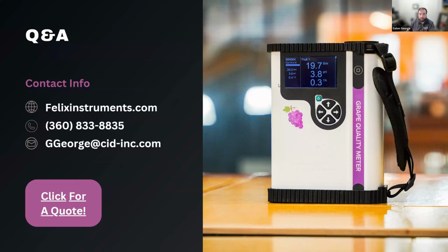This is a great question. I already kind of addressed that, but is there any specific requirement on the light condition? Your experience with similar NIR technology based equipment is that the measurement is largely affected by the ambient light environment. That is why we developed this proprietary device that has an internal reference shutter. This internal reference shutter is used at the start of every single measurement that we take. And what it's going to do is it's actually going to baseline every single measurement based on the ambient lighting conditions. And so it zeroes out those ambient lighting conditions. So regardless of if you take one measurement outside and then the next measurement inside on the same fruit, it will give you the same result. So there is no external lighting condition calibration needed or anything like that.